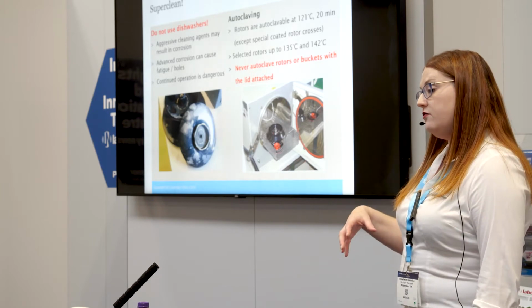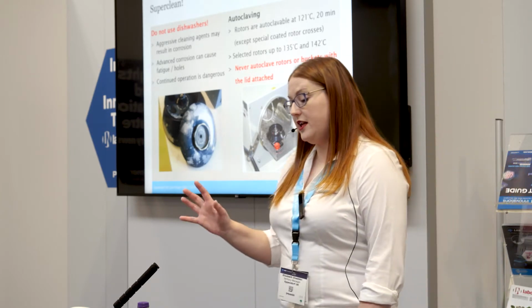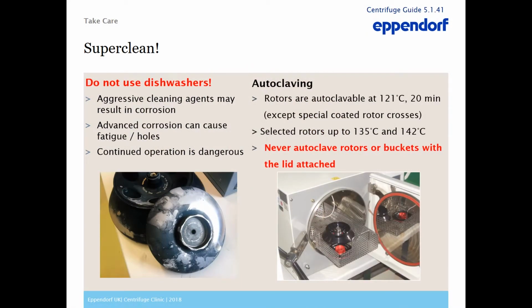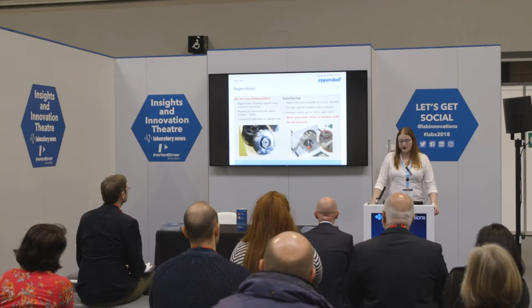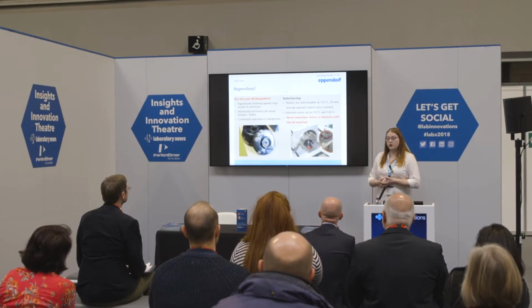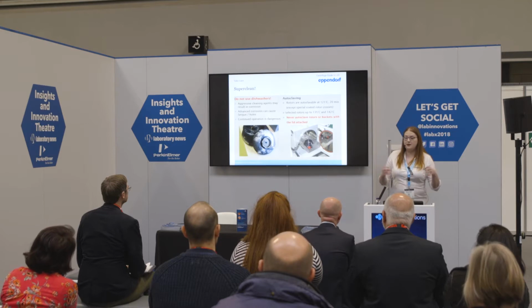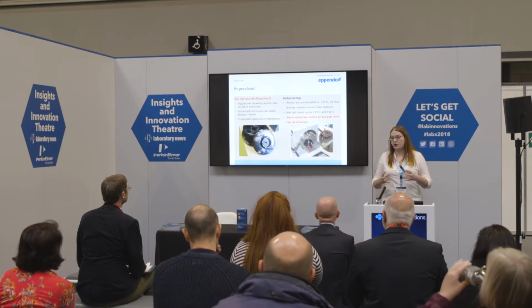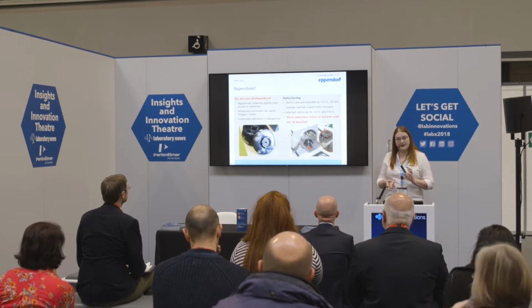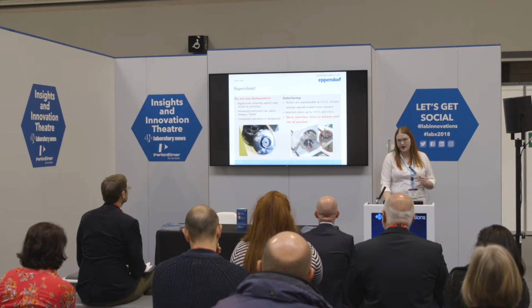When it comes to our set of rotors, they are autoclavable at 121 degrees, and some of them up to 135 or 142 degrees. It should be in the manual that comes with the centrifuge, if that is possible. If not, ask the manufacturer and we will be able to tell you. But don't autoclave them together, because heating up the rotor and then cooling back down again can cause things to lock together, and it makes a mess and it's not easy to fix.